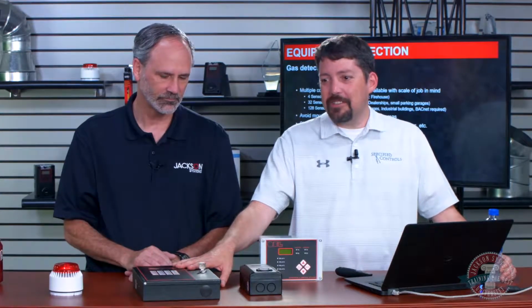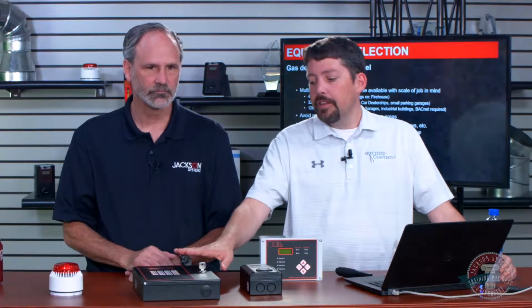We should always avoid mounting control panels in common areas, just because people are curious and they start pushing buttons. We don't want that. So yes, it's code protected and it's locked and all those things, but if you can avoid it, don't just put it out in the common space. And it should have the capability of programming alarms and relays and whatnot. The manufacturer should always provide pre-programming of the system for the contractor.